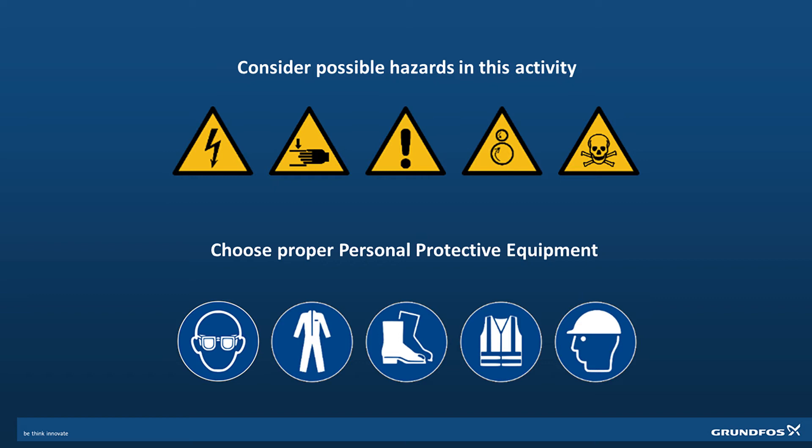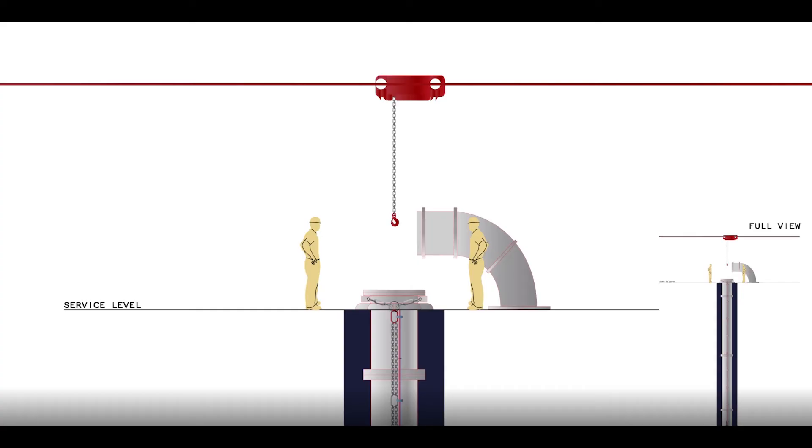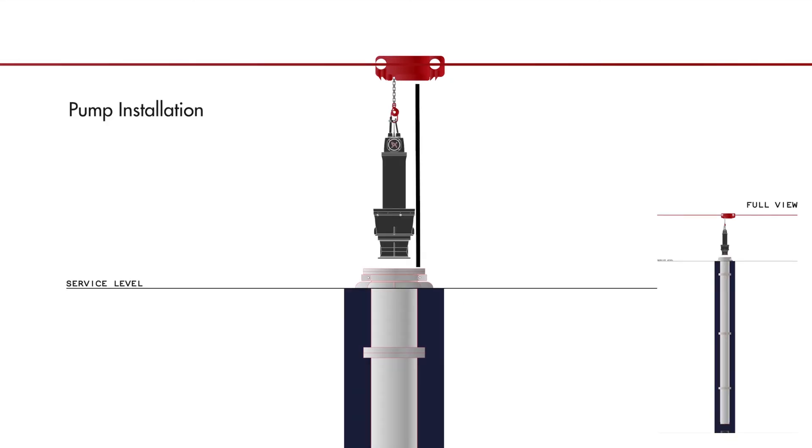Before lifting and handling the pump, it is very important to check personal safety equipment and to secure that the crane and other lifting equipment is in good condition and suited for the weight of the pump and the cables. It also requires some height above the column tube for both the pump and the lifting crane, as tilting the pump to install it or take it out of the column tube will compromise personal safety and might damage the pump.